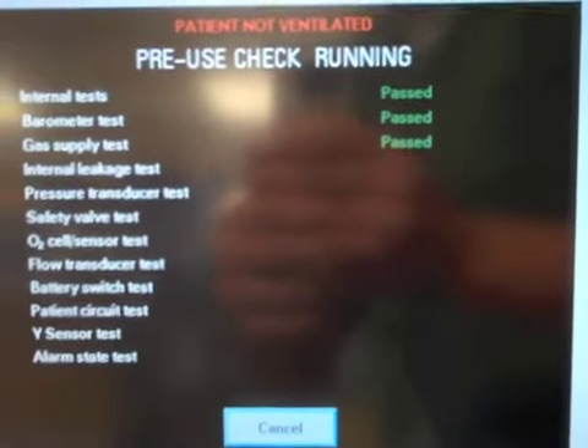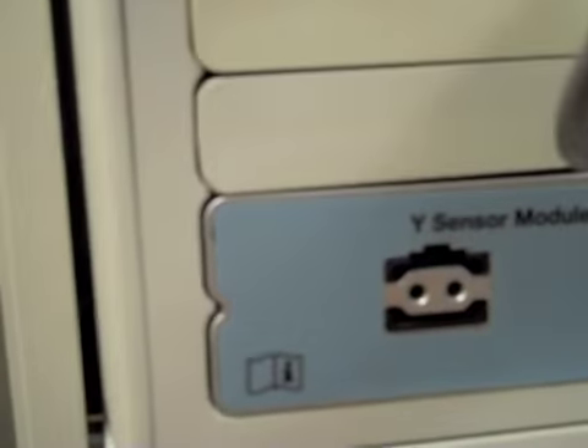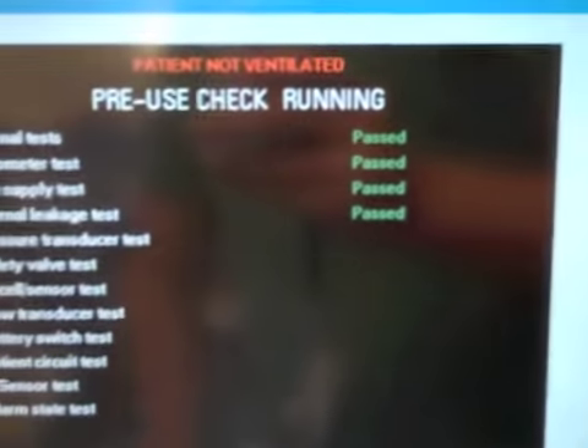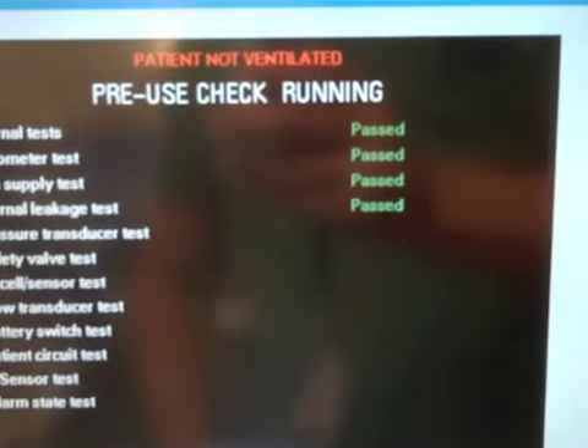That's another external piece. So on the side of this, you'll actually see some modules. If you come down here, you'll see one that says Y sensor module, and you can plug a cord in there to make it a little bit more accurate, a little bit more sensitive. Let's say if you're doing neonatal, you can put a flow sensor right at the patient Y. For our purposes, we're not going to do that test. Everything is going well so far. I'm getting passes.